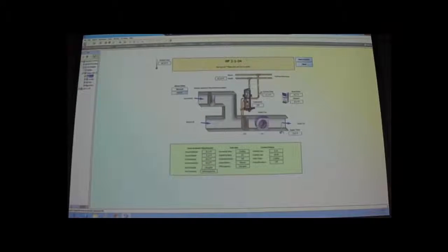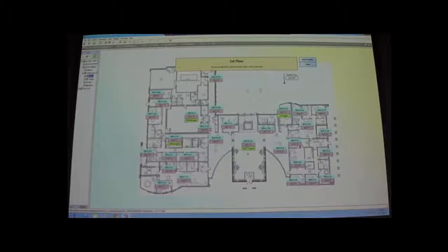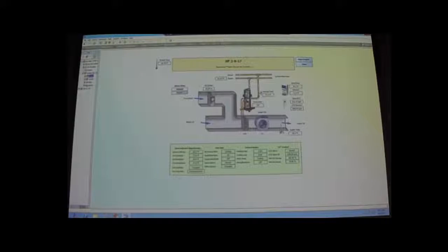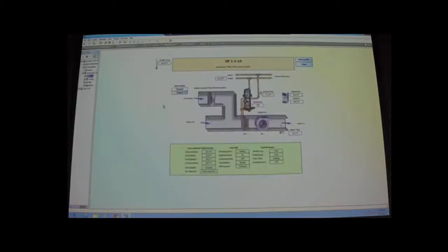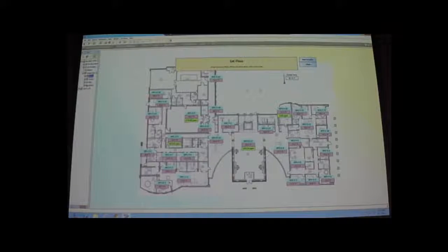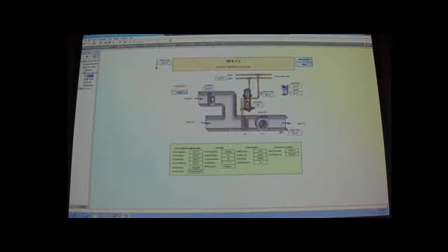And like I said, they're all pretty much the same. The CO2 heat pumps, you can see that it's got the outside air damper position. The units that do not have CO2, it just has a fixed damper with a little note that it's a fixed position. And then the econ units, these guys here, the E7-1. So you can see that one's got an outside air damper position on it as well. However, these are actually using the outside air damper positions to cool.